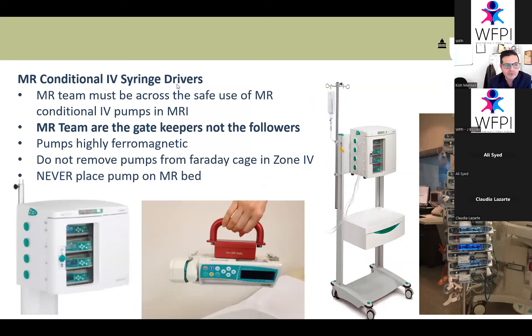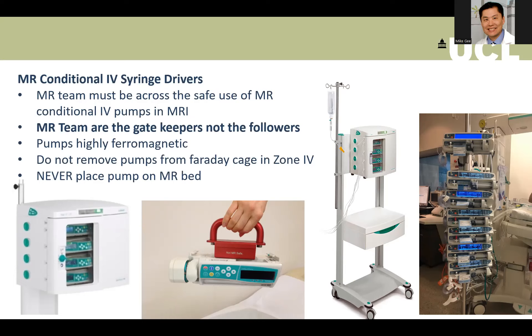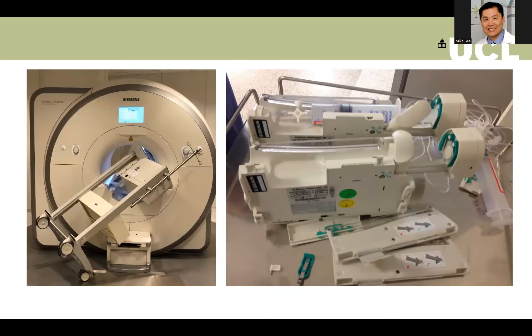Regarding conditional IV syringe drivers: the MR team is the gatekeeper, not the follower. Don't expect anesthetists or the intensive care team to decide what is safe to bring in. As the MR team — whether radiographer, tech, or radiologist — your decision is enabled by local practice and correct labeling checked regularly. Even syringe drivers transported in a Faraday cage are not completely safe; catastrophic events can still occur, as demonstrated in one reported case.